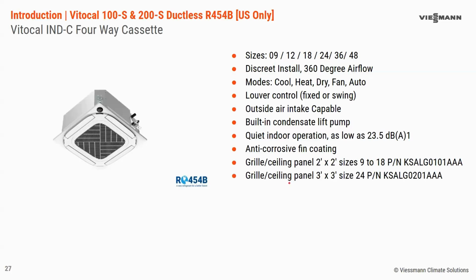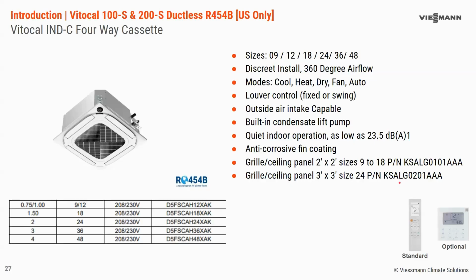One call out with this four-way cassette is to ensure that you have the proper ceiling grill panel as well. So this is ordered separately at this time. We're looking at potentially having a kit created, but based on the market, we know that it's already included separately. So just want to call out these part numbers here. There's two grills, one for the 2x2 and one for the 3x3. These come standard with the wireless controller, optional for the wired, and your 5 sizes below with the 9 and 12,000 BTU being dip switch selectable capacity.